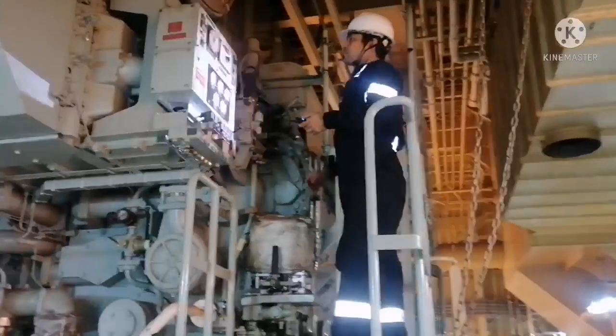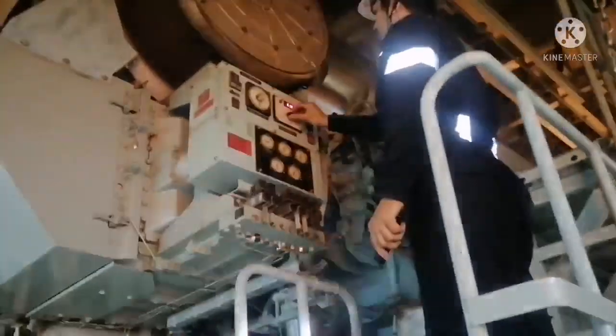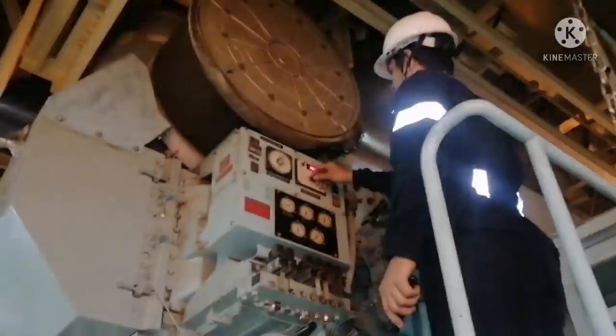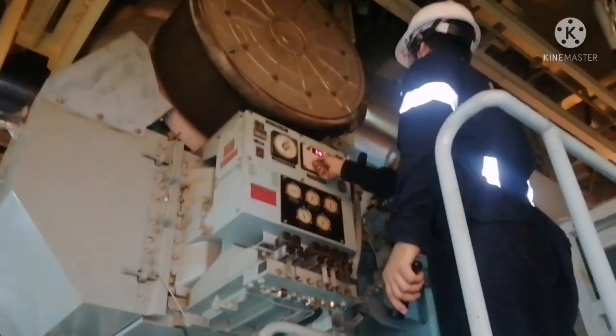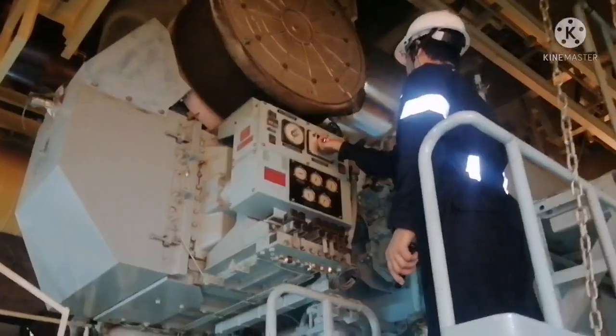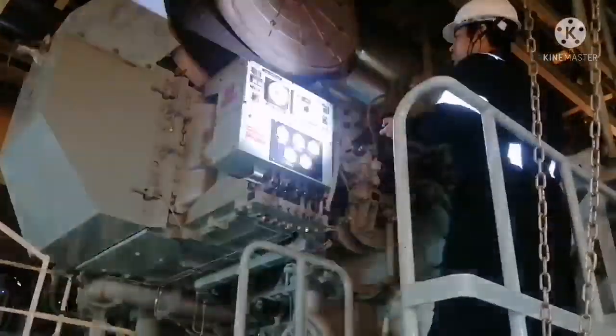Generators. Whichever is the running generator, as I said earlier, you have to check the parameters, and whichever generator is on standby, you have to check the standby light is glowing and the lube oil priming pump is running and everything. For the running generator, you have to check the exhaust temperatures and everything.